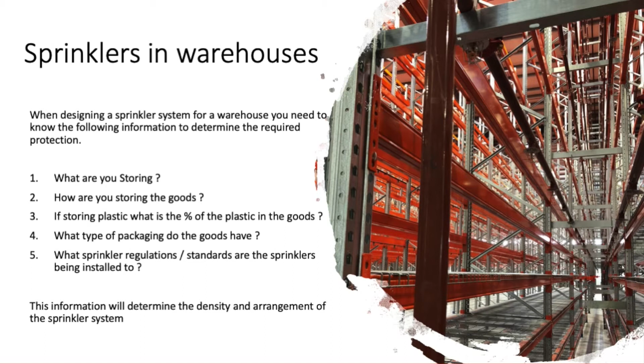In America, we've got NFPA and FM standards. NFPA is the national standard, and FM is by the Factory Mutual Insurance Company. Both standards are driven through live fire tests — they set stuff on fire and put it out with sprinklers, and they learn through that. American standards are generally limited to buildings up to 15 metres in height, as in America land's cheaper, so they tend to have larger footprints because they're buying more land. So warehouses in America cover quite a big area.